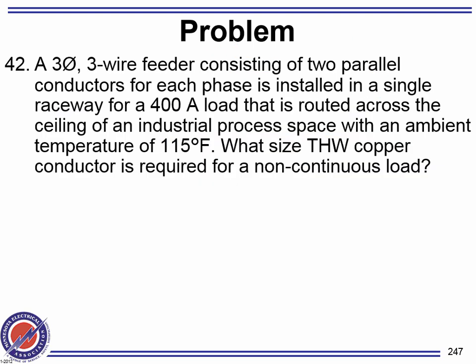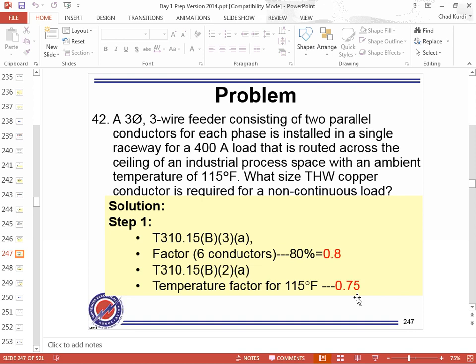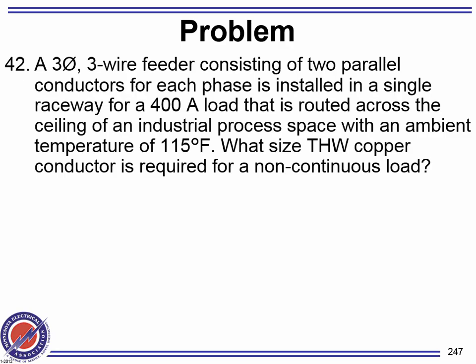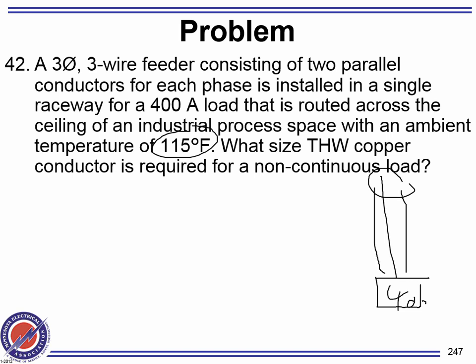All right. Here's an example. We have two sets, parallel sets. So we have two machines, and we fed these machines from one feeder. Two parallel sets, 400 amp. So what happened, guys, is we have a machine that we're bringing two parallel sets of circuits for. It's a 400 amp. Ambient temperature sucks. We put all these conductors in one conduit when we came to it, which is okay. So the question is, what conductor do I need to carry this machine? There are two parallel sets. So how much will each set be carrying by itself? 200 amp, right? We'll be carrying 200 amp.